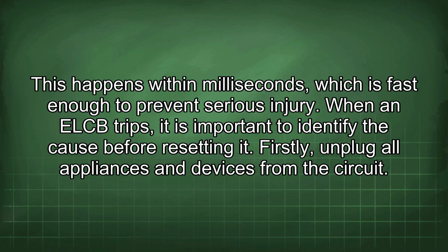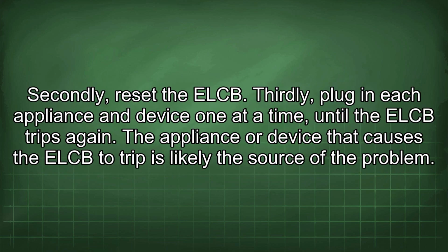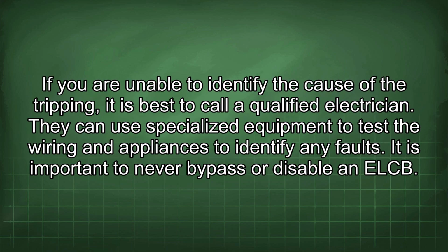When an ELCB trips, it is important to identify the cause before resetting it. Firstly, unplug all appliances and devices from the circuit. Secondly, reset the ELCB. Thirdly, plug in each appliance and device one at a time until the ELCB trips again. The appliance or device that causes the ELCB to trip is likely the source of the problem. If you are unable to identify the cause of the tripping, it is best to call a qualified electrician. They can use specialized equipment to test the wiring and appliances to identify any faults.